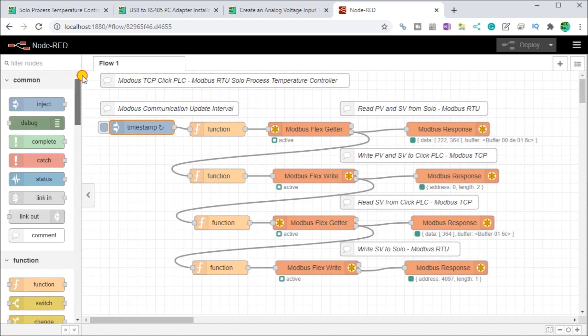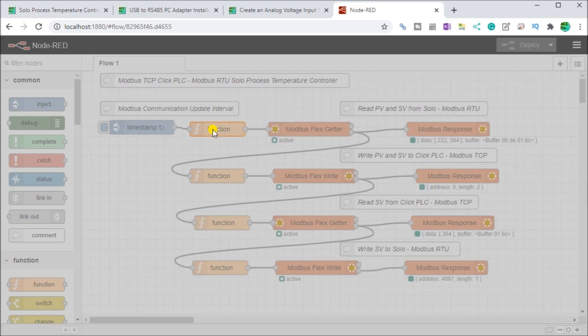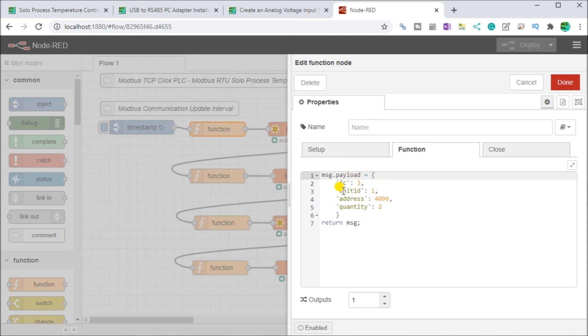The first node in our flow is a function node that sets the parameters for the Modbus flex getter. Double-clicking it shows function code 3 (FC3), which is the Modbus read. Our unit ID is 1, address is 4096 — which is the Modbus address for the Solo controller — and the quantity is 2. We then return this as our message payload. Those familiar with Modbus will recognize these parameters.